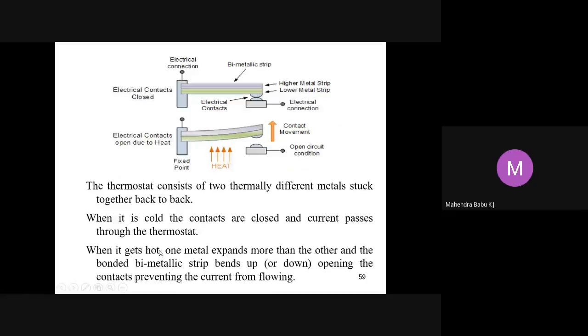So how does this thermostat work? A thermostat consists of two thermally different metals stuck together back to back. You can see here, two metals are held together. When it is cold, the contacts are closed and current passes through the thermostat. When it gets hotter, one metal expands more than the other and the bonded bimetallic strip bends either upwards or downwards, opening the contact, preventing the current from flowing. Here you can see the electric contact when it is closed, and the electrical contacts open due to heat. When it is heated up, this bimetal will bend either upwards or downwards, thereby opening the contact.